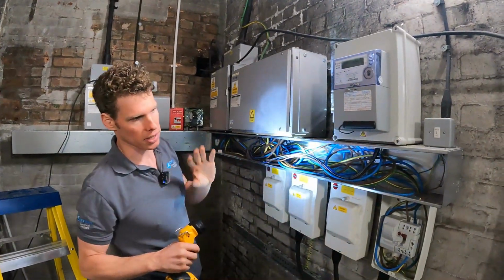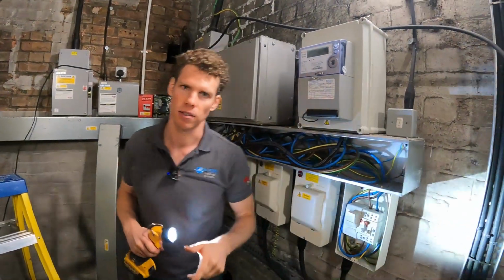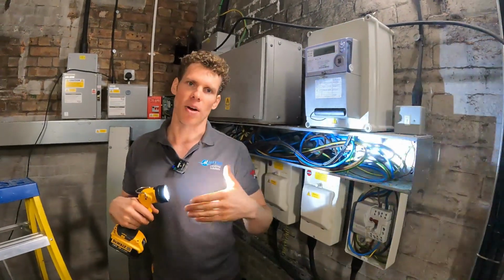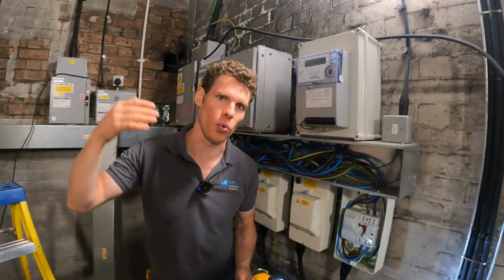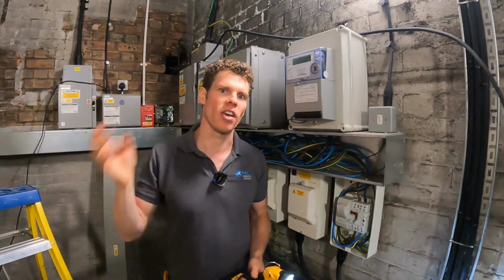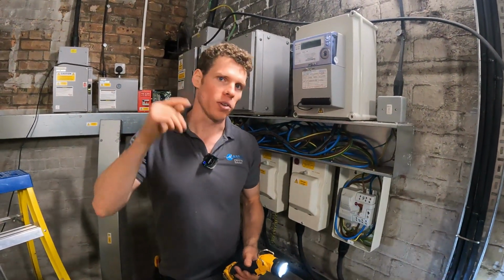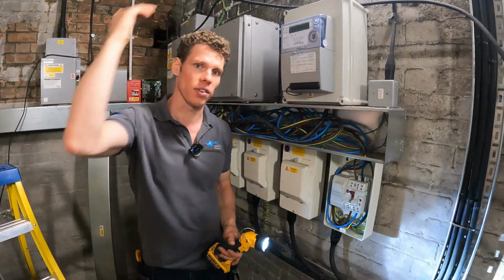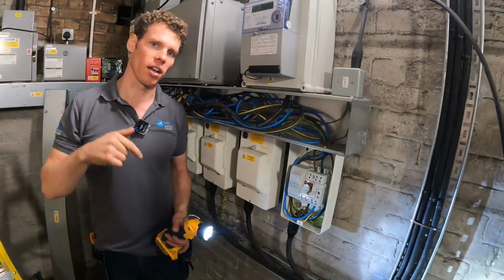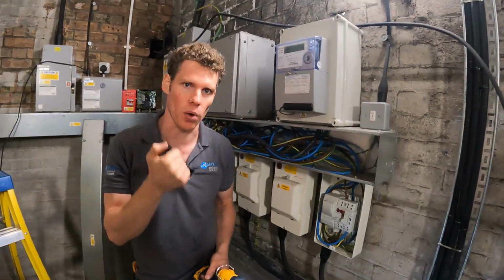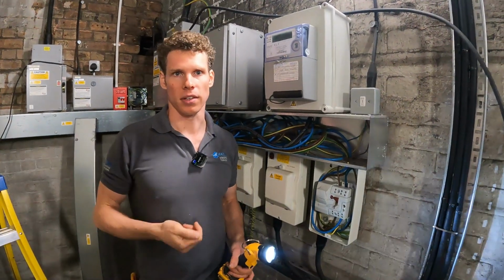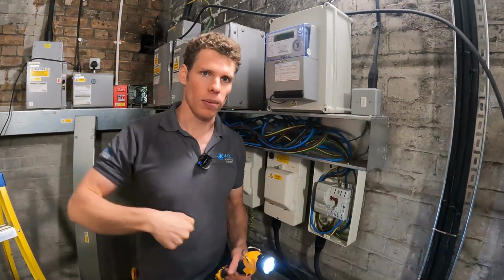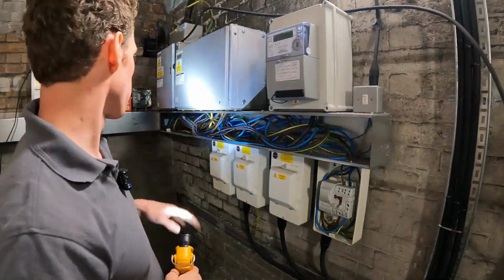What we're going to do first is an R2 wandering lead test. Now, I do all my regular Zs tests, but when you've got loads of switches and light fittings, it's not reasonably practicable to remove every one to check you've got an earth. So a top tip: do your percentage check of Zs on the circuit - go to the end of the circuit and do your Zs test as normal. But one thing I like to do is an R2 wandering lead test, because it's a very quick way of ensuring your earthing system is correctly connected. So we'll get the wandering lead set up, put it onto the MET, and get wandering around. Let's do that.